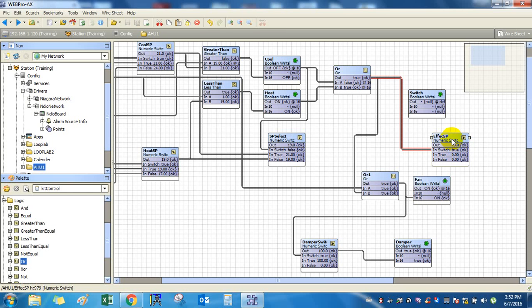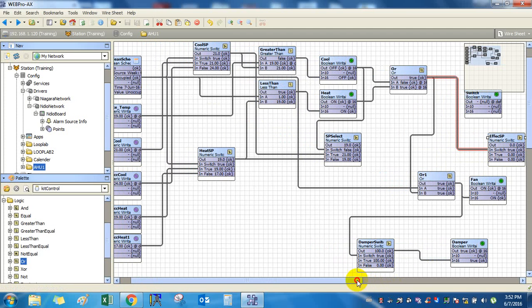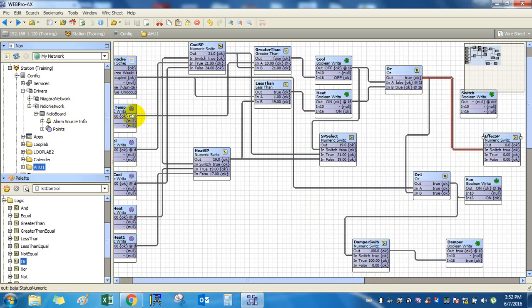Okay. This is a very simple AHU. Most of the time in your applications you will have to expand on this logic. A lot of interlocking will come, a lot of priorities will come, right? But this is just a very simple logic presented to show how we do it in JACE. You could add multiple levels to that, like the damper in here, where we have just chosen from 0% to 100%. It could be a modulating output, right? A lot of changes will happen in an actual field condition in this logic. Any more questions?